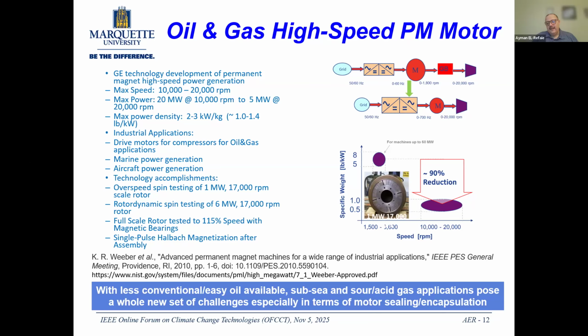Recently in this industry, you can see a transition to new systems that use advanced power converters operating at high frequency, up to hundreds of hertz. The gearbox is eliminated, which is usually a good thing since gearboxes mean a lot of maintenance in any application. Now the motor can be fully or directly integrated with the compressor, but that means using high-speed motors—instead of 1800 RPM, you can go up to 20,000 RPM or so.